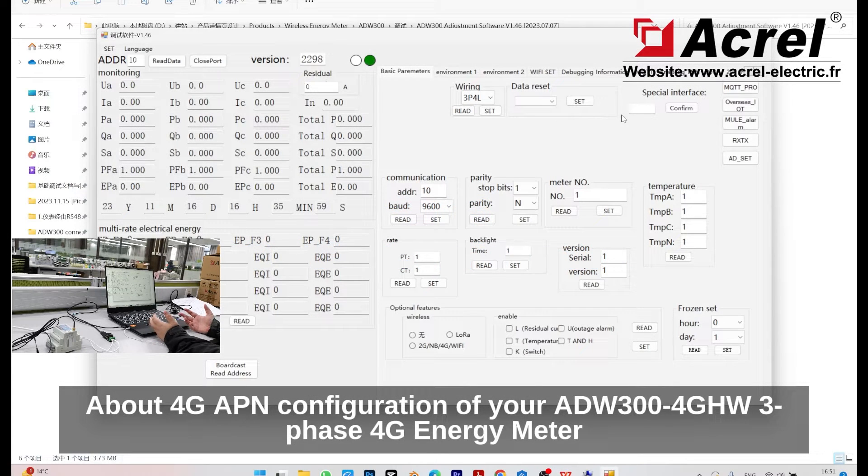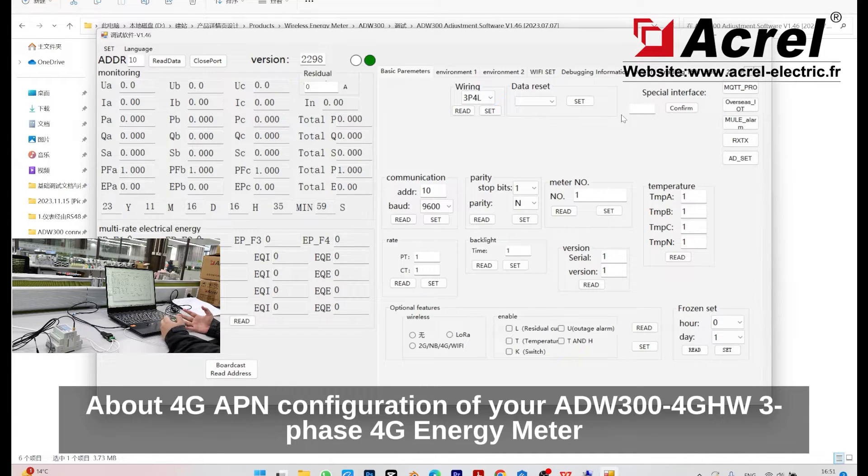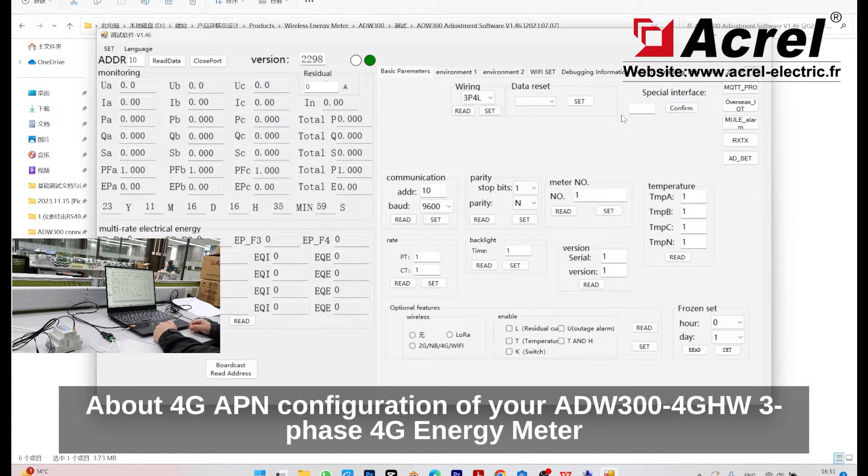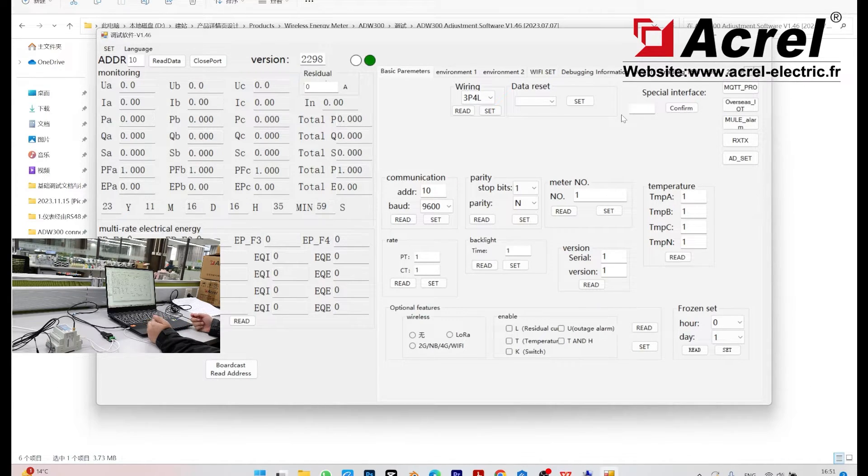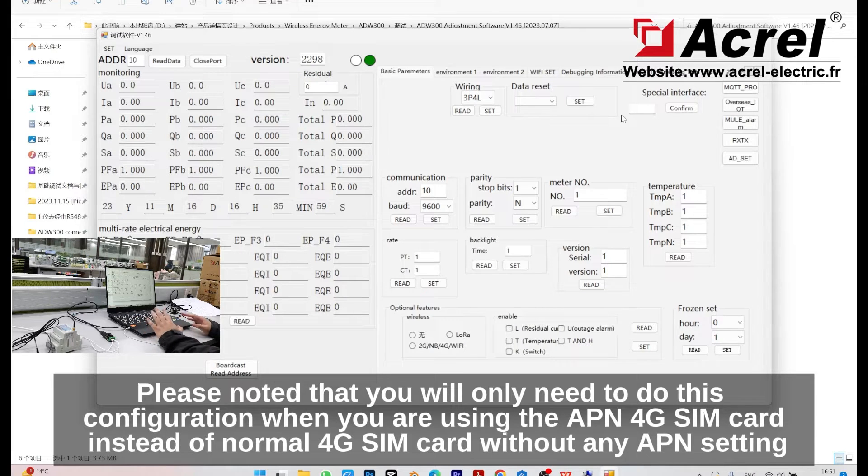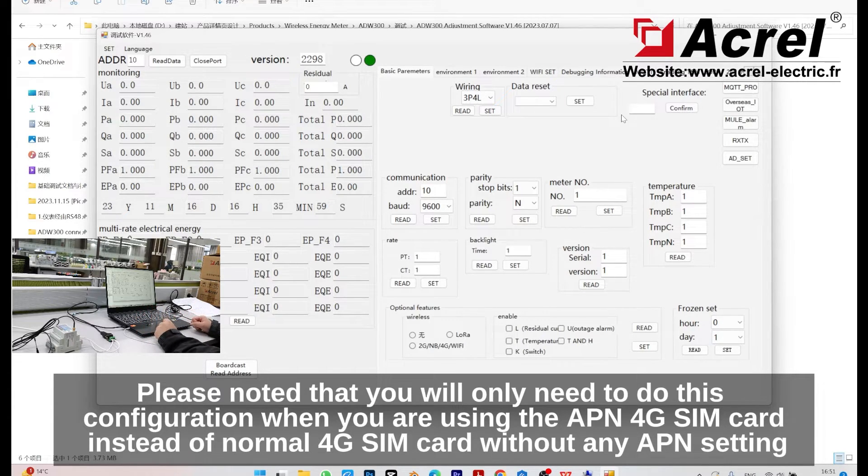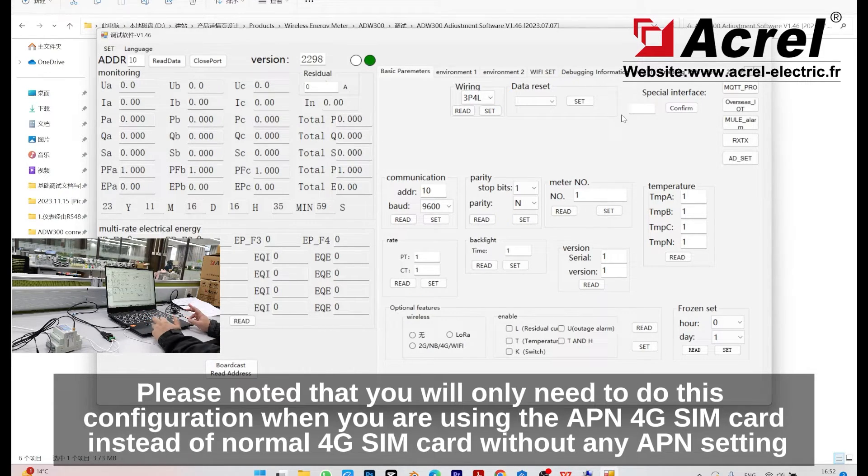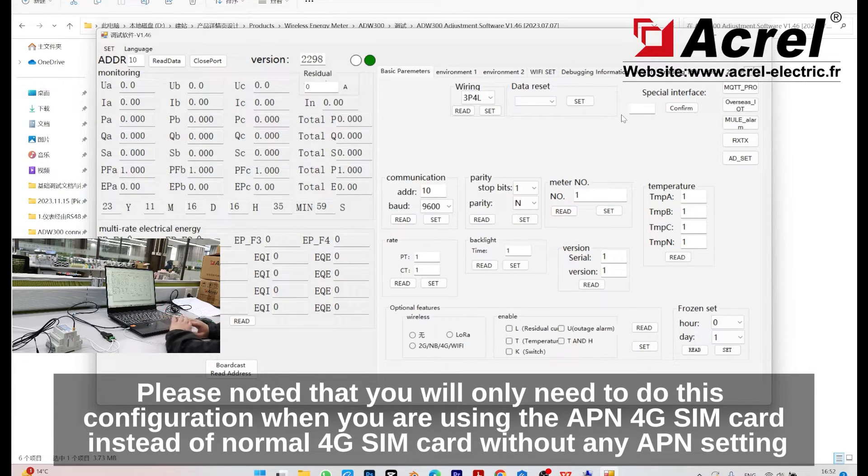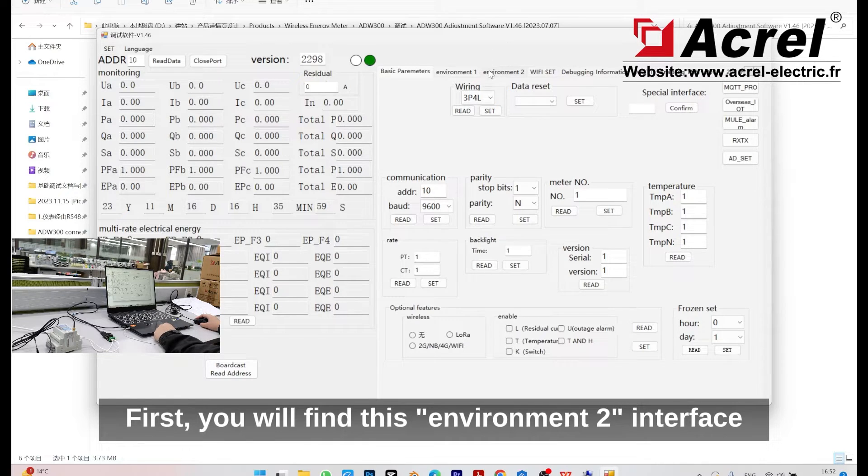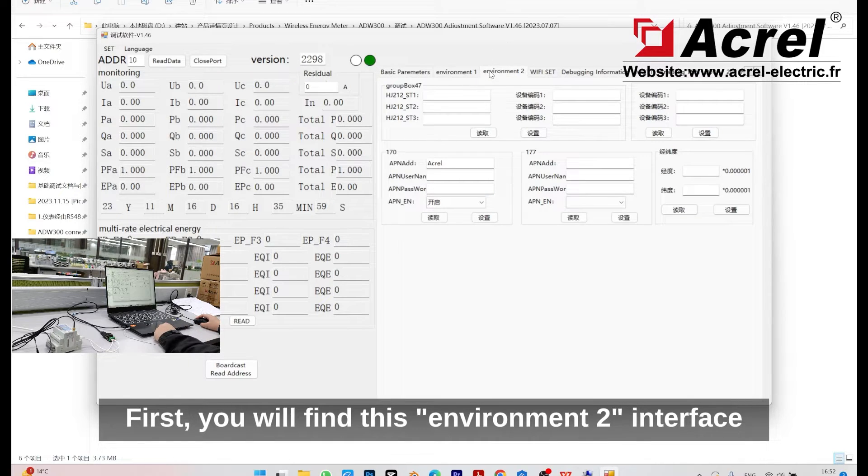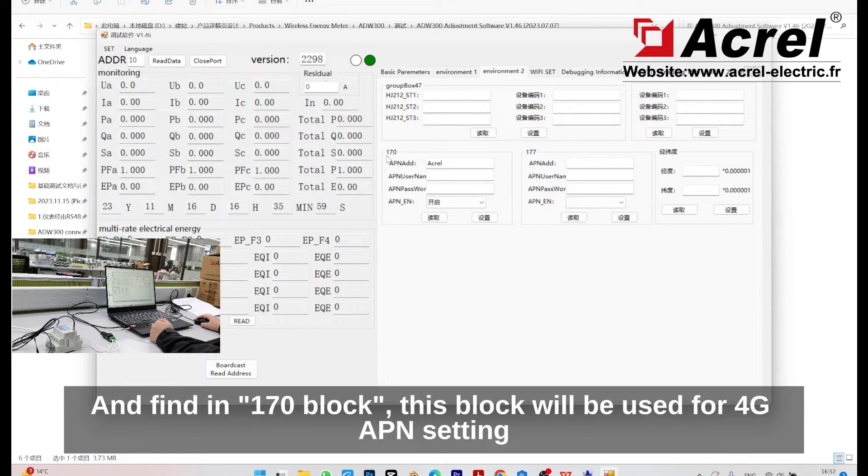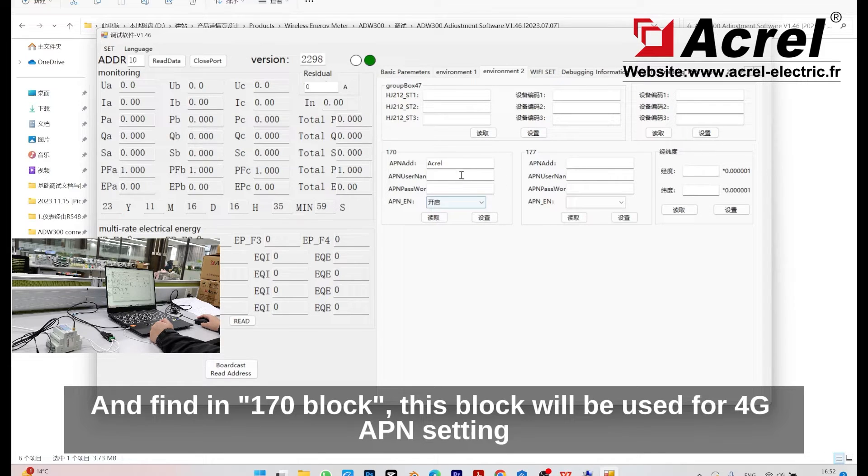About 4G APN configuration of the ADW300-4GHW three-phase 4G energy meter. Please note that you will only need to do this configuration when you are using an APN 4G SIM card instead of a normal 4G SIM card without any APN settings. First, find the environment 2 interface and find the 170 block. This block is used for 4G APN setting.